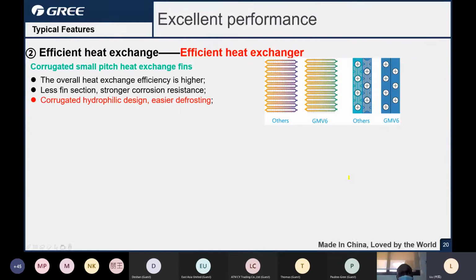Next one is about the heat exchanger. Okay, first one is about the fin. Now let's have a look here. For the others, you can see these two, maybe not very clear, but I can tell you that for the GMV6, the tube diameter is smaller than the other brands or the previous GMV5, because now we use the 5.7 copper tube, so that the efficiency of the heat exchange will be higher, because the smaller the diameter, the better the heat exchange performance.